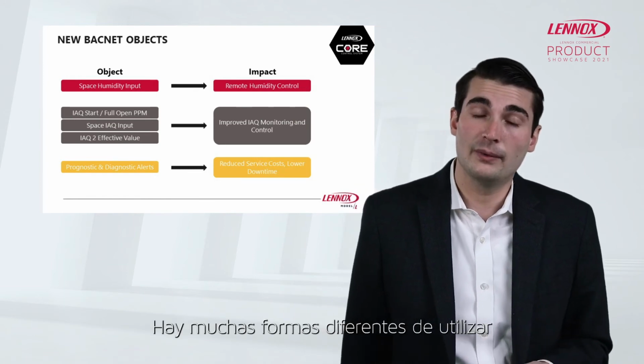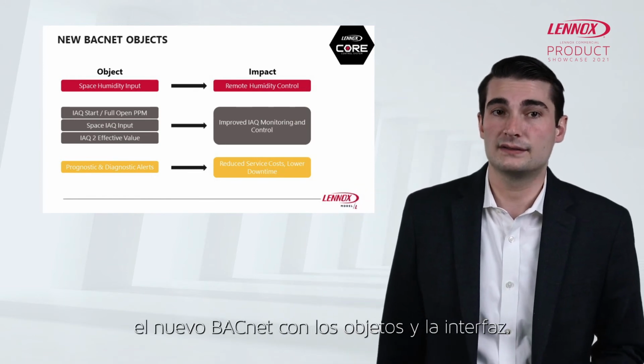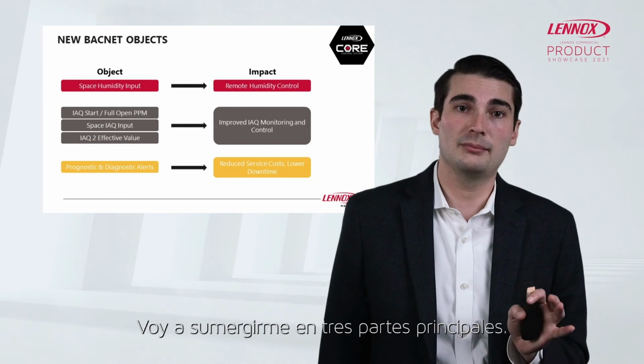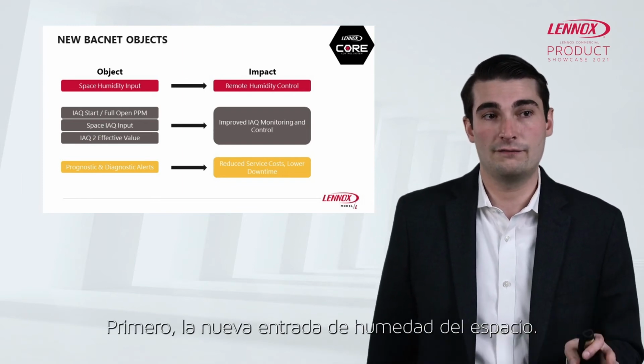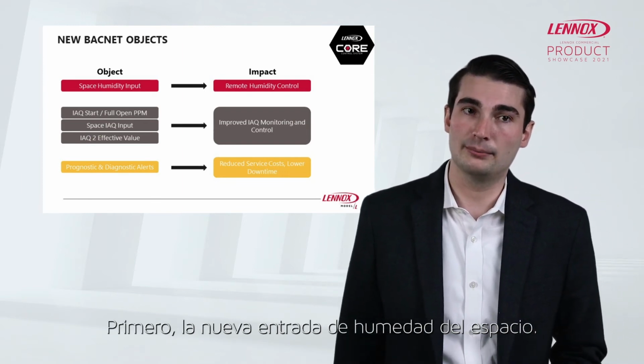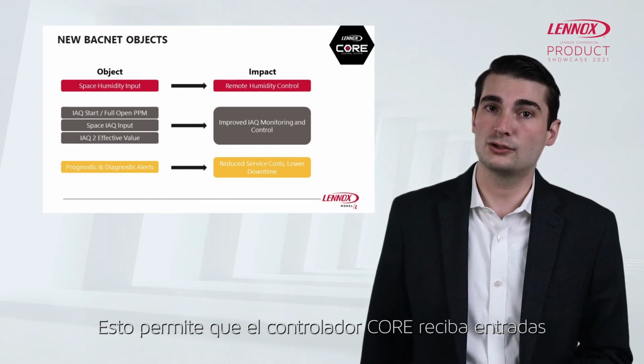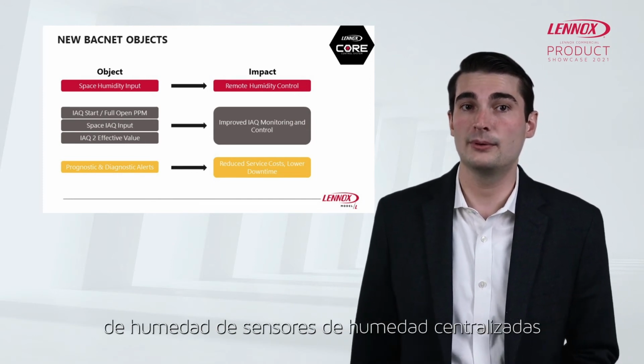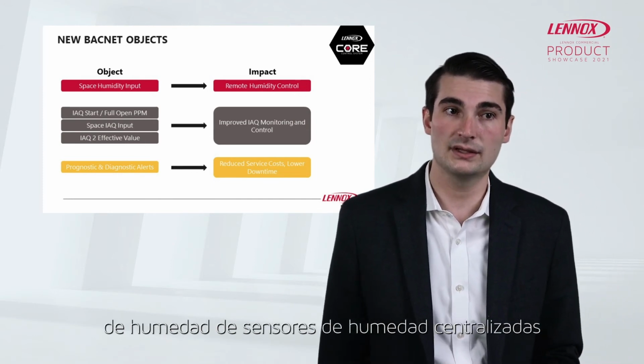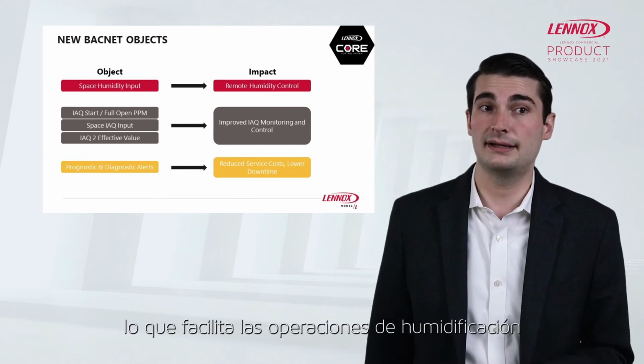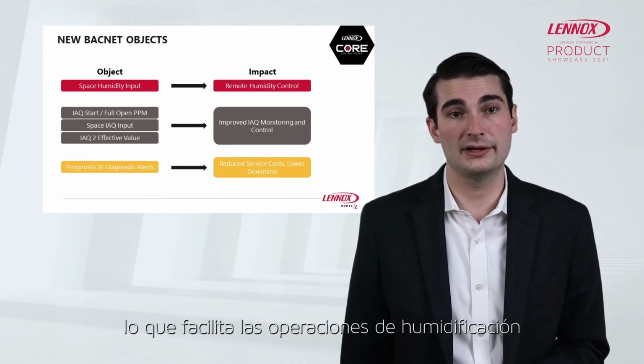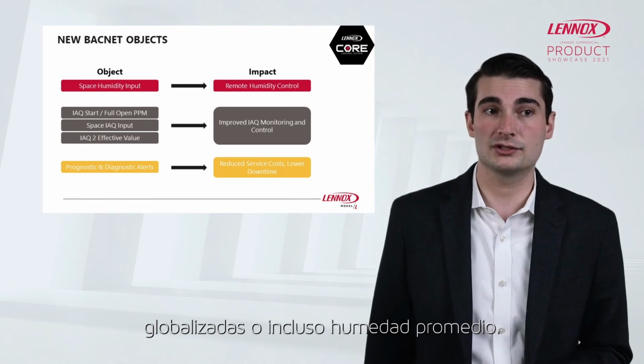While there are many different ways to utilize the brand new Bacnet objects and interface, I'm going to dive into three main parts. First, the brand new space humidity input. This allows the Core unit controller to receive humidity inputs from centralized humidity sensors elsewhere in the building, facilitating globalized dehumidification operations or even humidity averaging.